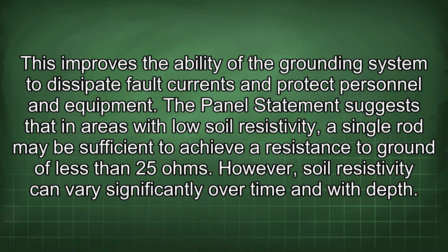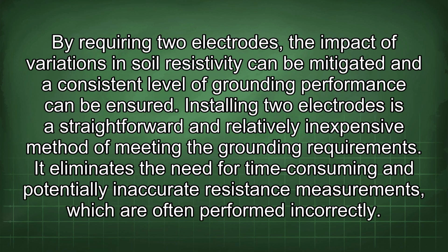The panel statement suggests that in areas with low soil resistivity, a single rod may be sufficient to achieve a resistance to ground of less than 25 ohms. However, soil resistivity can vary significantly over time and with depth. By requiring 2 electrodes, the impact of variations in soil resistivity can be mitigated and a consistent level of grounding performance can be ensured. Installing 2 electrodes is a straightforward and relatively inexpensive method of meeting the grounding requirements.